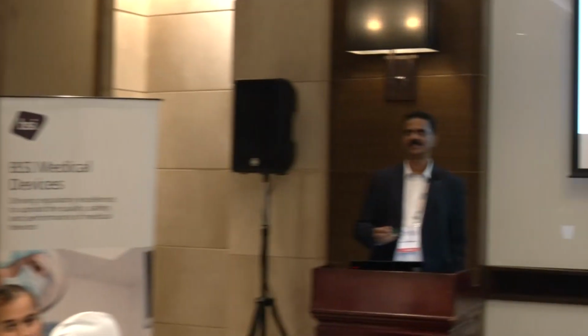So what information from your perspective would you be looking for in the clinical evaluation plan or report from the risk management file? For the risk management, we'll expect what kind of residual risk you identified, then how you address it, how it affects the clinical performance or the clinical safety, and also your risk benefit profile. How do you justify your risk benefit profile? That's what we'll expect, only the brief information.